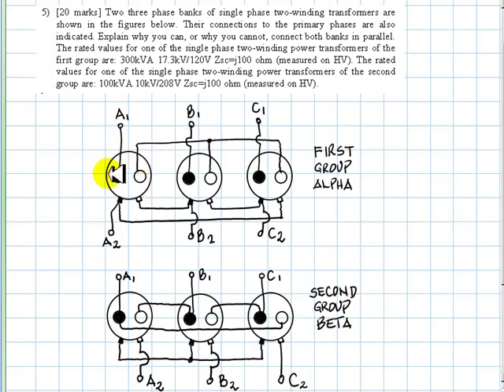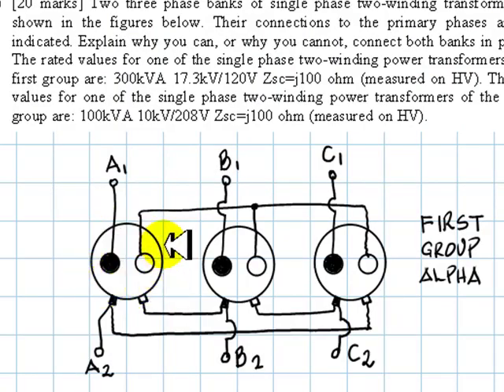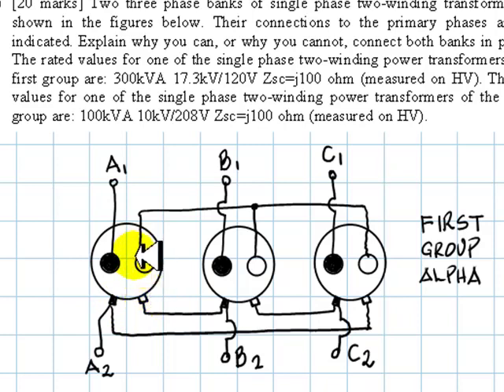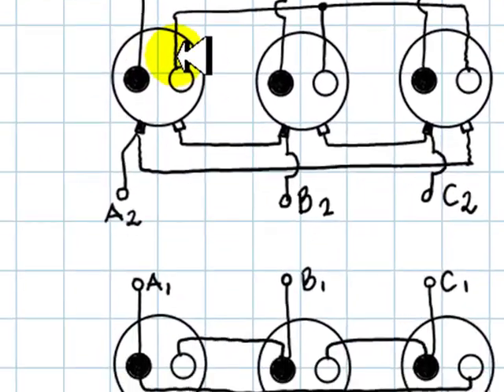The rated values for one of the single-phase transformers of the top group (Group Alpha) are: 300 kVA power rating, 17.3 kV on the high-voltage coil, 120 volts on the low-voltage coil. The short-circuit impedance of this transformer is j100 ohms measured on the high voltage side.